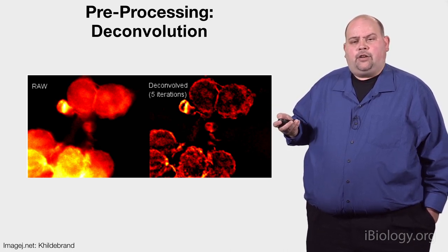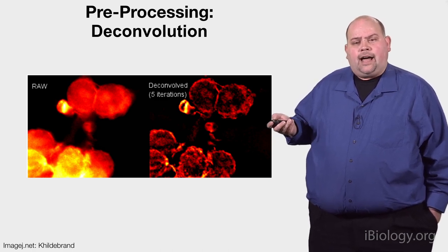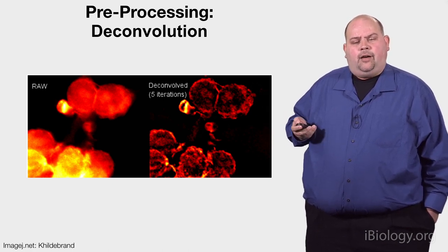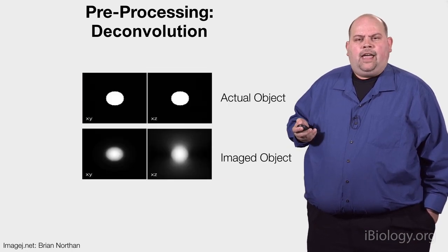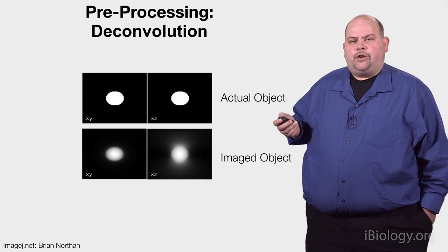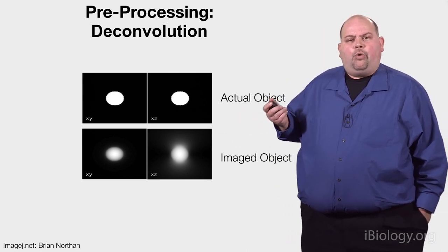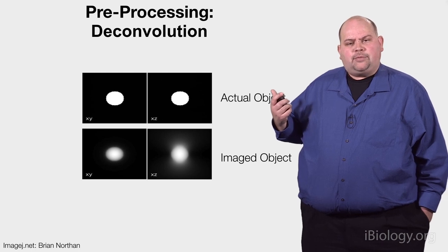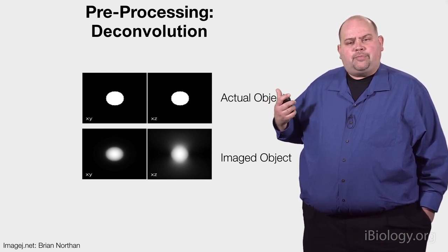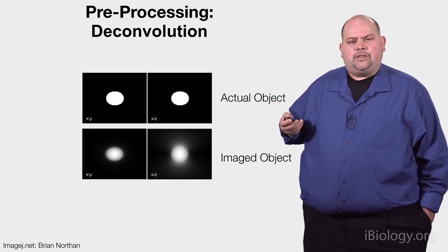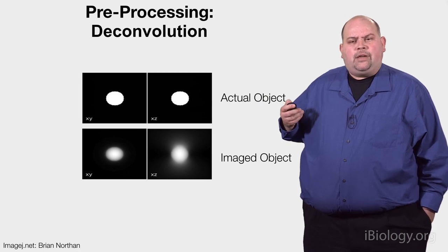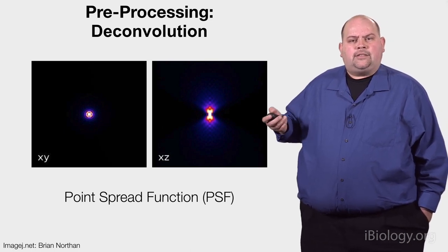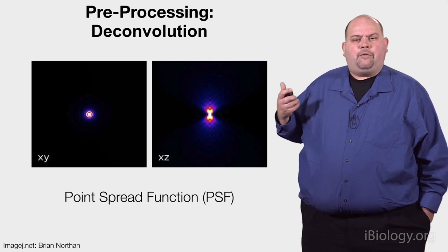And this can be very important because it can often result in why your microscope may look more noisy or have less contrast than a colleague's microscope that seems to have similar capabilities. You want to be able to see smaller features, for example, and that can be prevented by problems due to convolution or noise introduction. And so what you can do in this kind of work is understanding, for example, a basic bead and trying to understand what is the actual object you're trying to measure. And trying to measure what's called a point spread function, basically this mathematical measurement of what is your point spread of your sample. Understanding in Z what is the error produced by error of your optics, your actual glass, issues like optical oil or things being left on that might contaminate your view, and we can correct for that. We can understand this mathematical function and then use other algorithms to gather the point spread function to correct for the inherent convolution of your system. So think of it as a way for correcting the error of your optics.